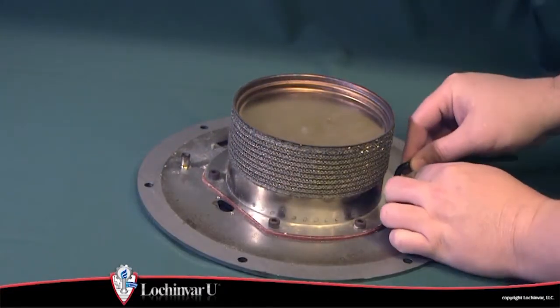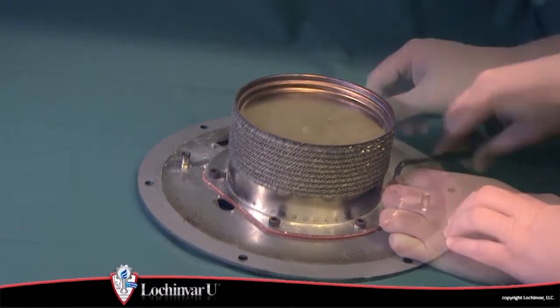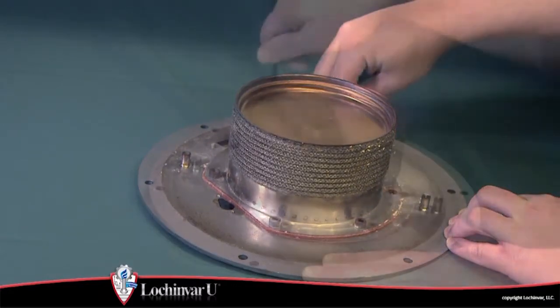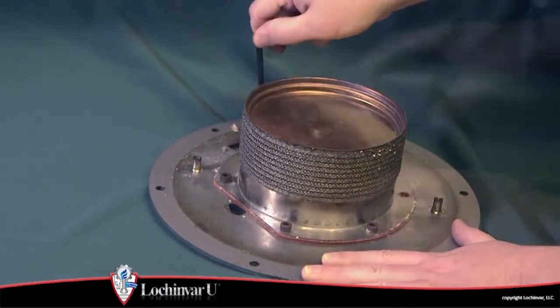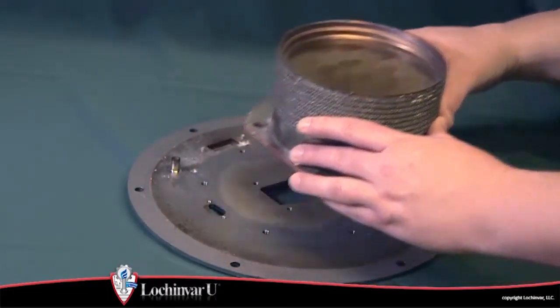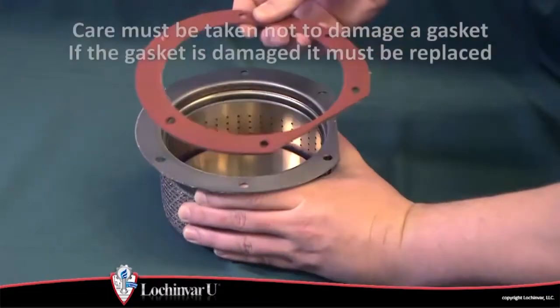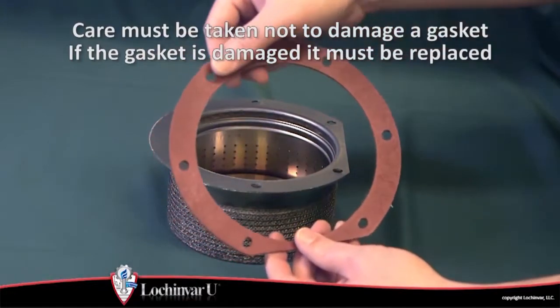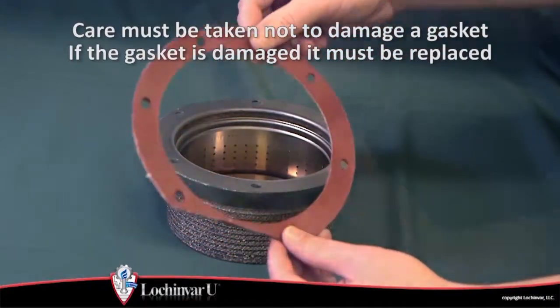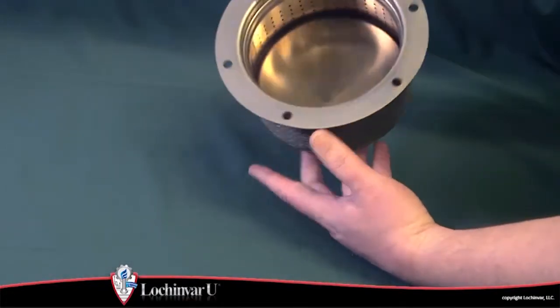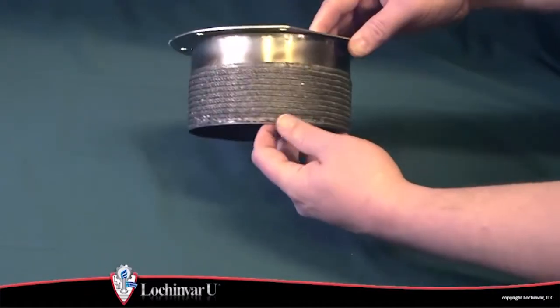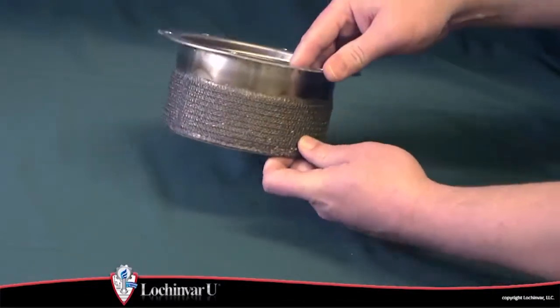Now, using a 5mm Allen wrench, remove the 6 screws that secure the burner assembly to the top of the heat exchanger top plate. A gasket is used to seal between the burner and the heat exchanger top plate. Once removed, inspect the burner for any physical damage. If the burner is damaged, it must be replaced.